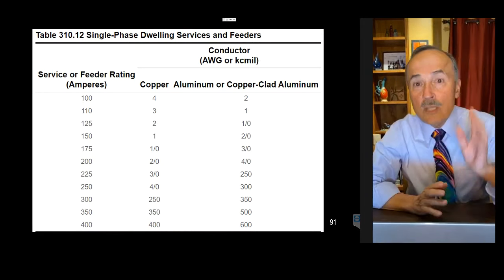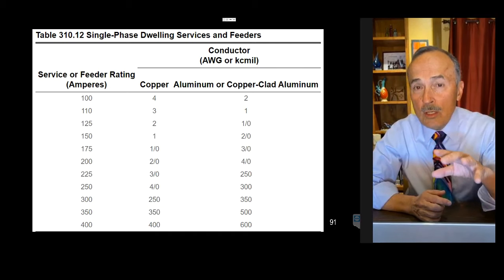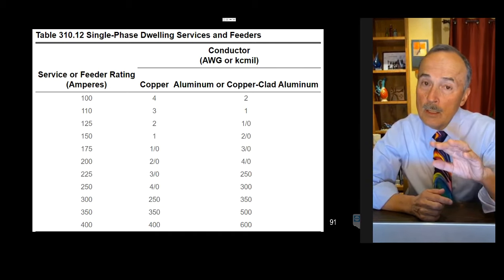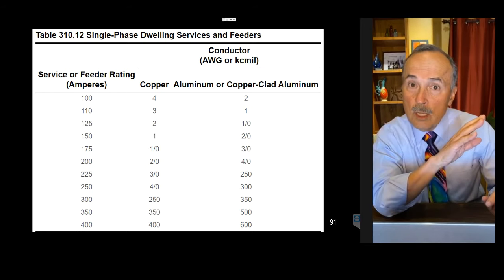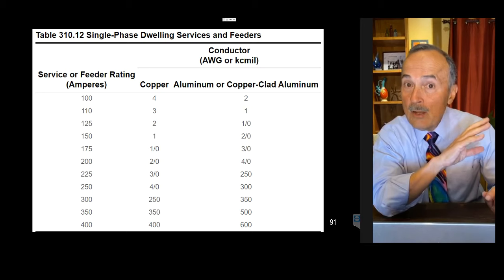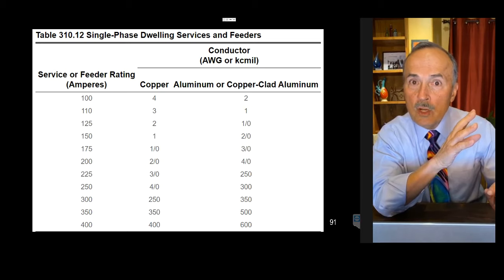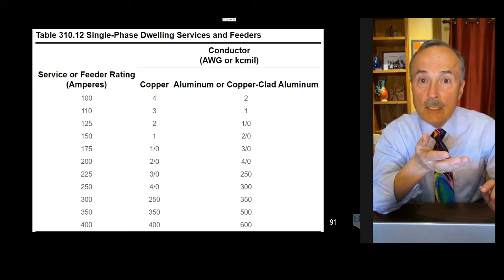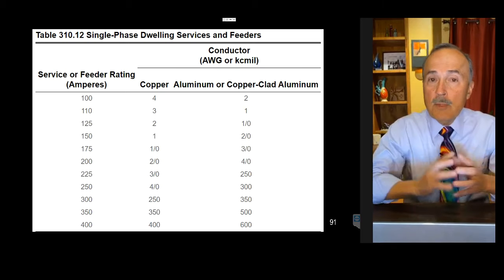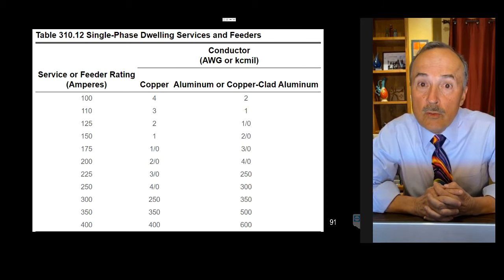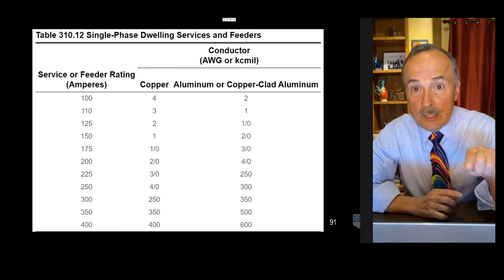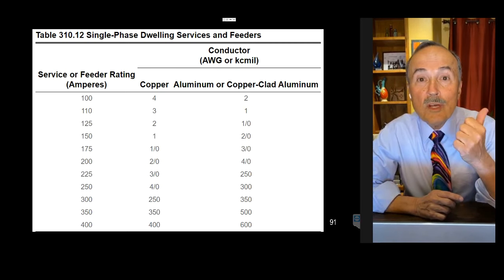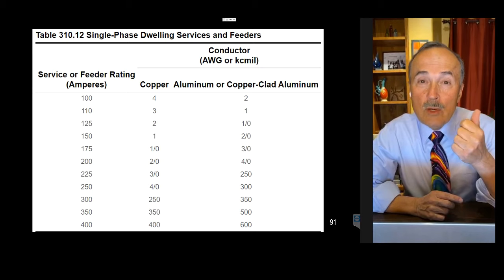Because conductors must be protected at the ampacity, which is 240.4, but a totally different code panel in 310 said, we've had this for 100 years. Here's the wire size you can use for residential, because we know that in residential you don't actually put on the current that you calculate. Hold on, that's not an Article 310 deal. That's an Article 220 deal, and how you size conductors based upon the calculated load, continuous and non-continuous loads. You don't put a 200 amp service and run wires smaller than the rating of the overcurrent device and use the next size up rule.